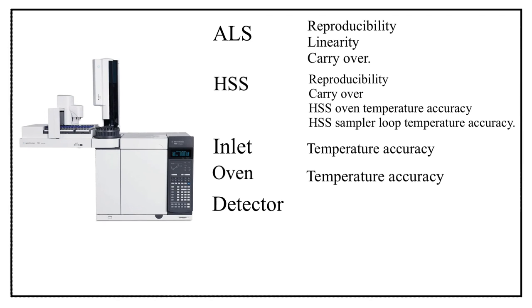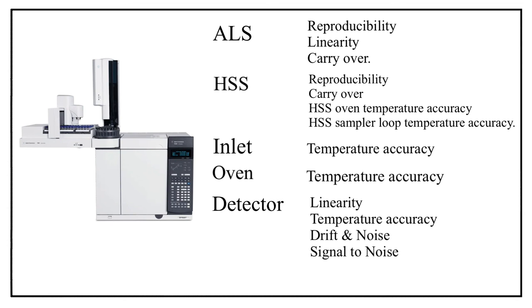The FID detector has four calibration parameters: detector linearity, temperature accuracy, drift, and signal-to-noise ratio.